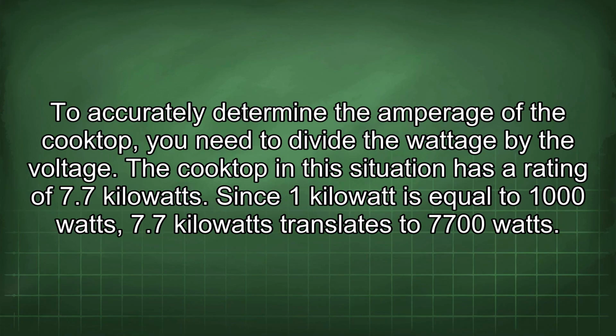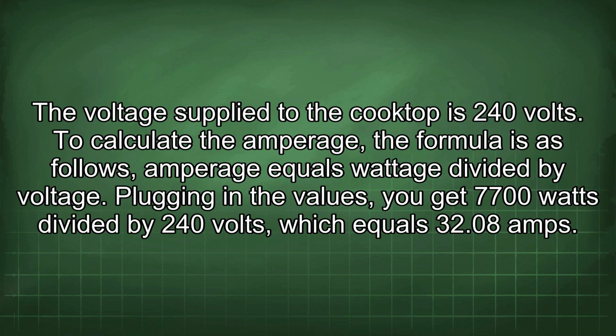To accurately determine the amperage of the cooktop, you need to divide the wattage by the voltage. The cooktop in this situation has a rating of 7.7 kilowatts. Since 1 kilowatt is equal to 1000 watts, 7.7 kilowatts translates to 7700 watts. The voltage supplied to the cooktop is 240 volts.